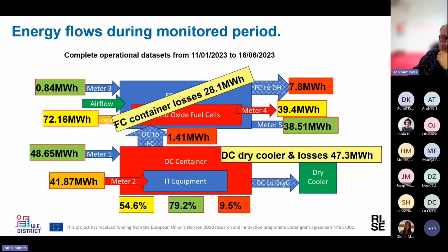In terms of the power meters, of that 39.4 megawatt hours, there were some parasitic losses in the fuel cell container: lights, etc., a small pump, monitoring equipment. Only 38.5 megawatt hours managed to be extracted to enter the grid. And of course, the data center being the nearest point of consumption, that was consuming 48.65 megawatt hours. So what we're saying is that we managed to cover 79.2% of the electrical requirements of the data center using the fuel cells. In terms of the IT, it was only consuming 41.87 megawatt hours because we had a dry cooler, we had a small heat pump in here to maintain the temperature of the container, and there were a few other parasitic losses to do with the monitoring system as well.